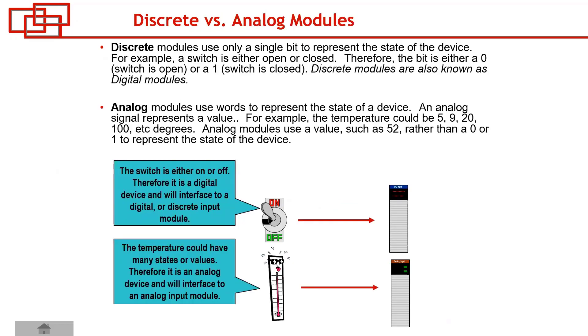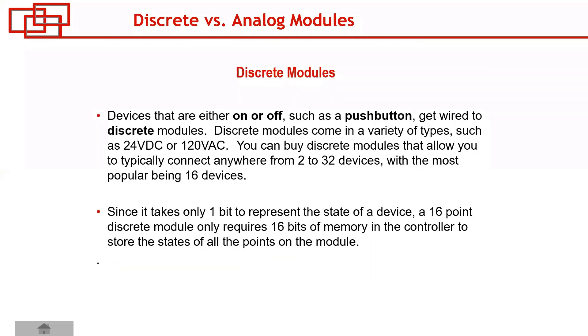There are two types of input modules: discrete and analog. Discrete means the signal is either high or low, open or close, running or not running — signals with two states fall under discrete. For discrete signals you require a digital input module. For analog signals, which are continuously varying — like temperature, level, pressure, or flow — you require an analog module. Analog modules use a range of values to represent the state of a device, such as continuously changing variables.